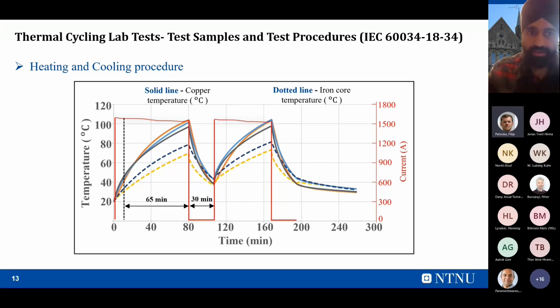And this solid red upper one is the other y-axis. This is for the current of the split core transformer, showing that it reaches near about 1500 ampere on this side. Then it turns off, and this is the cooling time, and again it turns on, and the temperature starts increasing again. So this is the test procedure for the temperature profile.